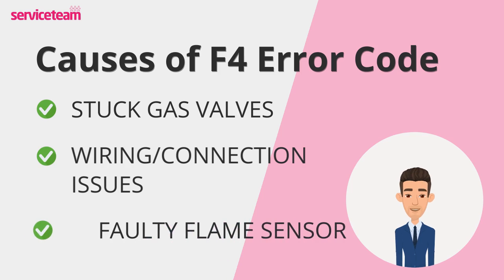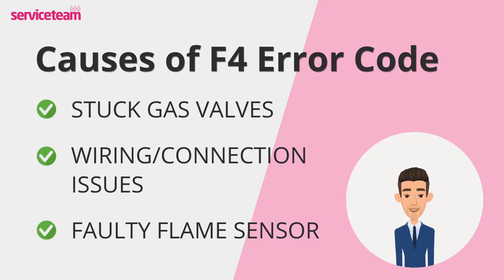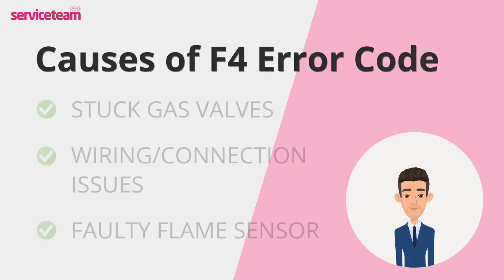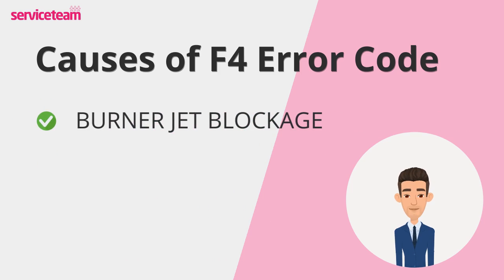Another reason for the F4 fault is a faulty flame sensor. The flame sensor, responsible for informing the PCB whether the flame is lit, can malfunction due to cracked porcelain insulation or a buildup of combustion by-products like carbon, which can trigger an F4 error. Small debris can also block the burner jets, which light the gas during the startup process — a blockage prevents the flame from igniting, causing the boiler to show an F4 fault.